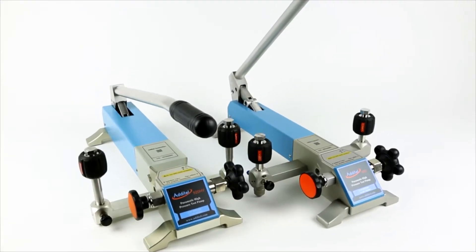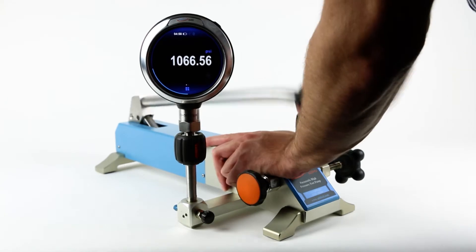The Additel 920HV High Volume High Pressure Pneumatic Test Pump is designed to generate pressure up to 3000 psi. The long handle allows for rapid pressure generation.